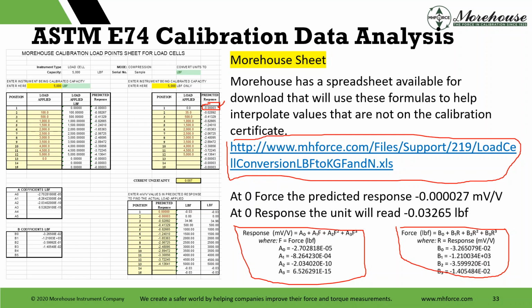However, if we look at the B coefficients here, look at this. This is where we're solving for pounds. So at 0, when the millivolt per volt value is at 0, we are not at 0 in pounds. We are at this B coefficient, which is negative 0.03. So if we put this on a meter and we tare the meter so that we're reading 0.0000 millivolts, our display should read, when we use this equation, negative 0.03, right? So down here in the predicted response, I show that.